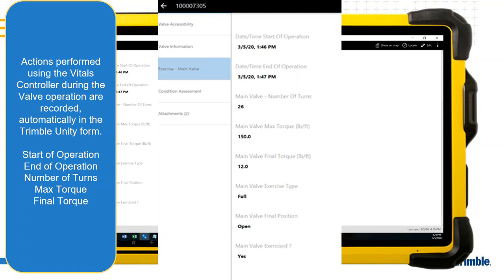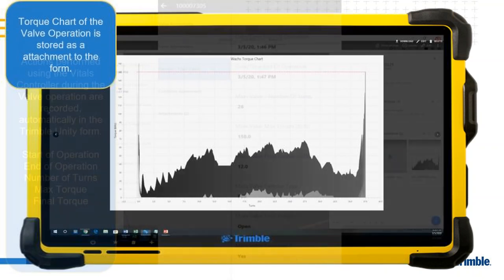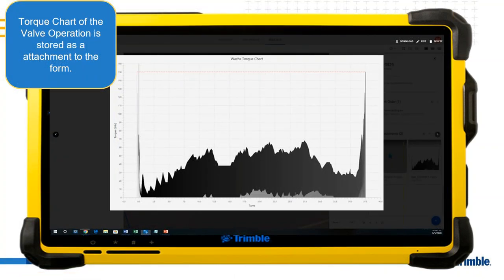Most importantly, it captures the number of turns the valve exercise machine performed, plus the minimum torque, maximum torque, and final torque during the operation. The Wachs machine stores and gathers very granular, precise data, and Trimble Unity makes sense of it — updating the form and presenting a graph of the entire operation, showing torque related to every single turn throughout the exercise.